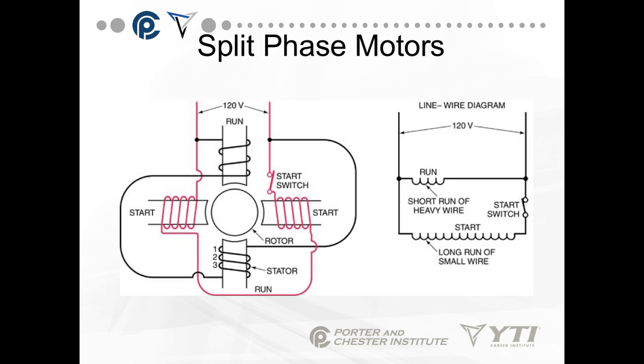If you looked at the inside of a motor, you would see the diagram on the left — run windings and start windings. Run windings are normally thicker wires with less turns. Start windings are thinner wires with more turns and have a start switch to pull the start winding out of the circuit. A ladder schematic of this would show the run winding in parallel with the start winding, and a start switch in series with the start winding.